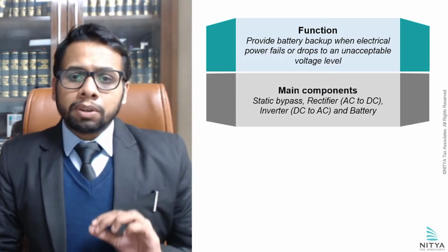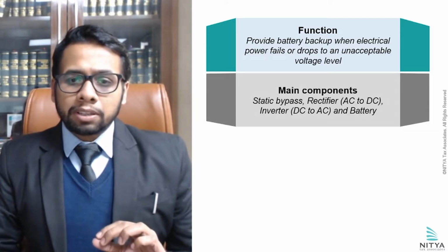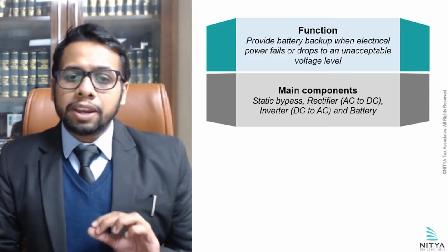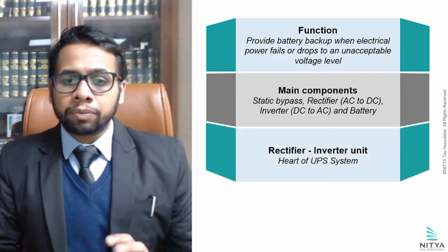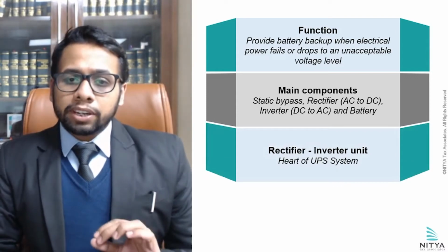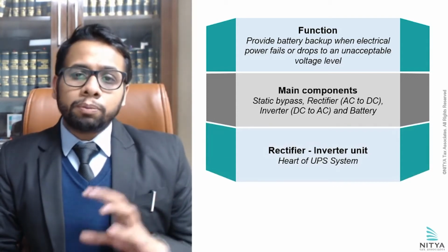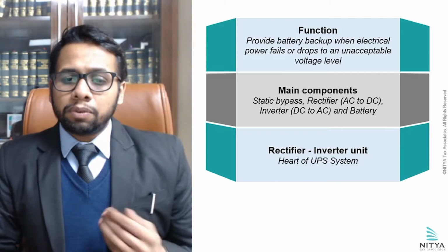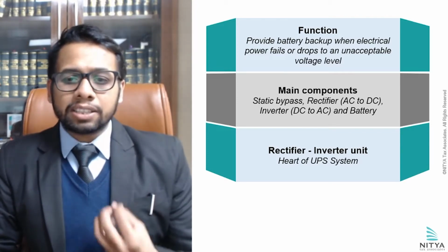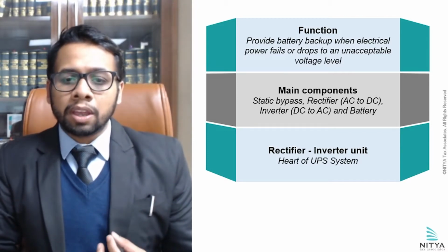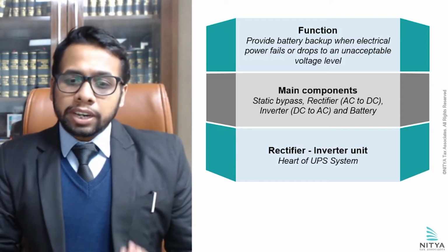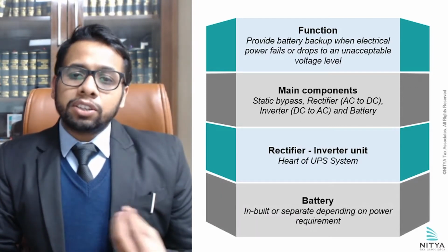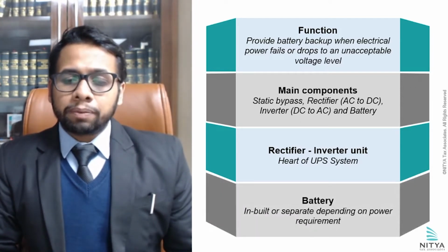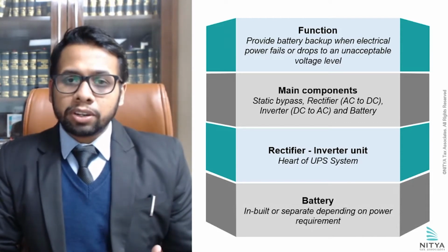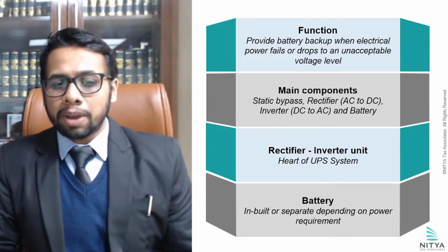The UPS system comprises a static bypass, a rectifier, an inverter, and a battery. The static bypass, rectifier and inverter form a single unit, that is an inverter unit, which is the heart of a UPS system. Apart from the rectifier-inverter unit, it has another component, which is a battery. The battery can be an inbuilt battery or a separate battery.